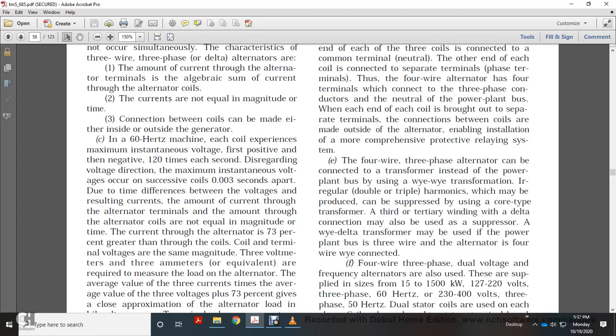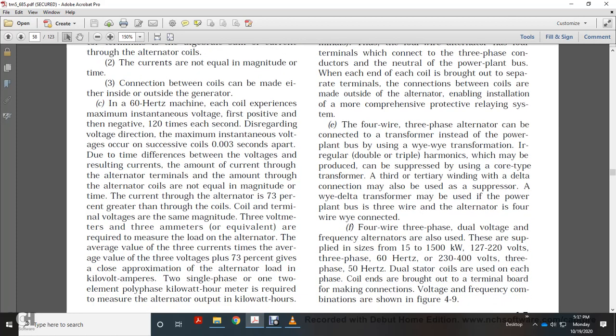Due to the time difference between the voltages, the current through the alternator terminals and through the alternator coils are not equal in magnitude at any time. The terminal current is 73% greater than the coil current. Three ammeters are required to measure the load of the alternator. The average value of the three currents times the average value of the three voltages, times 1.73, gives a close approximation of the alternator load in kilovolt amperes. Two single-phase elements in a polyphase kilowatt-hour meter are required to measure the alternator output in kilowatt hours.